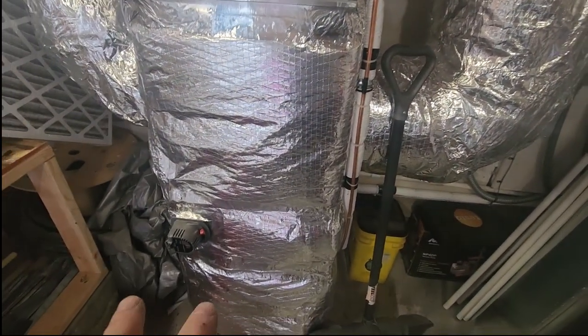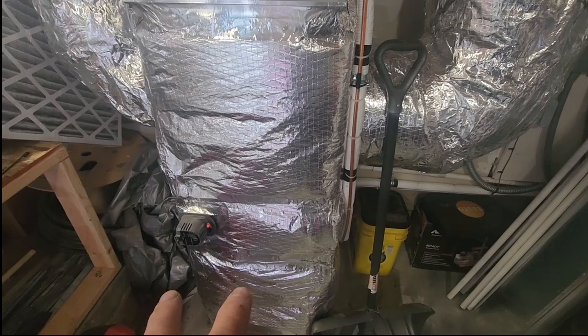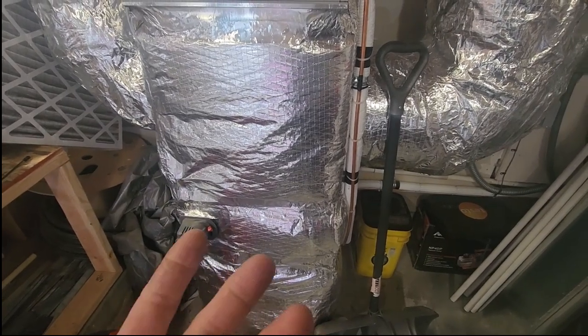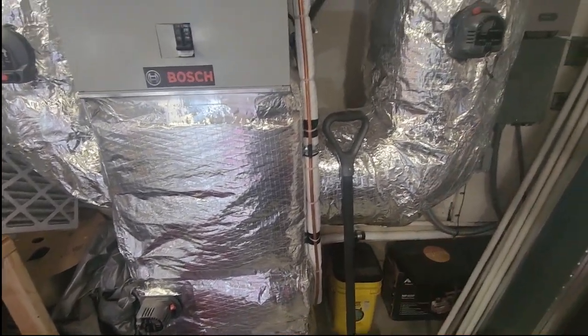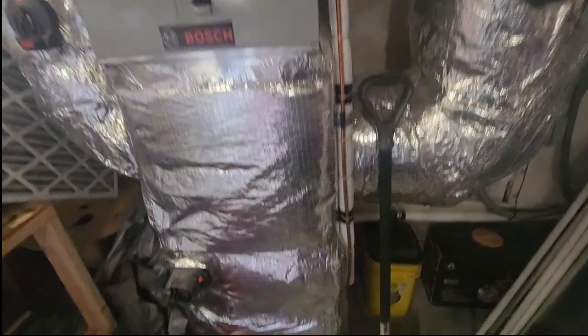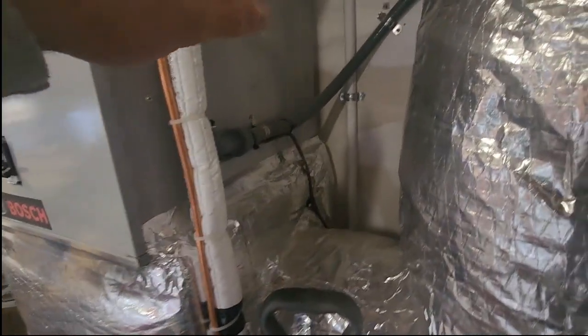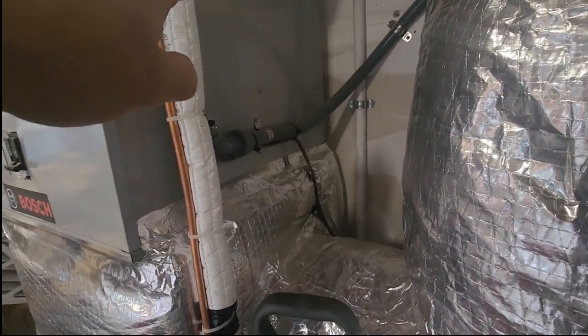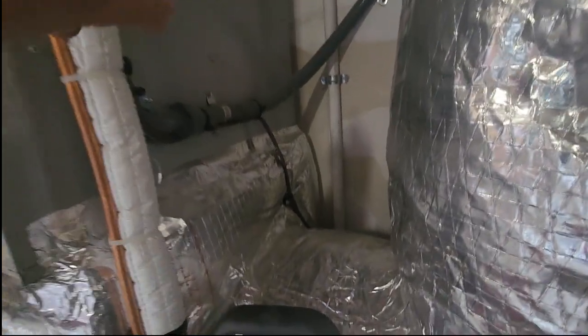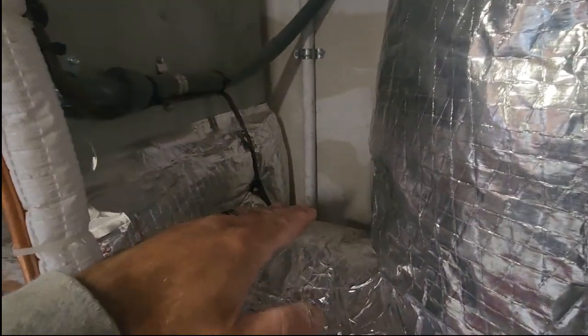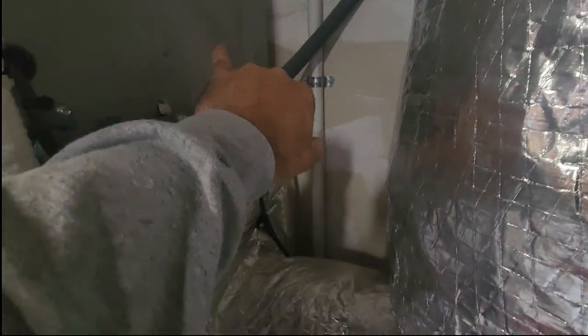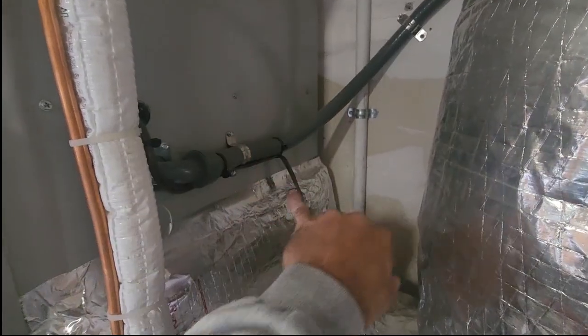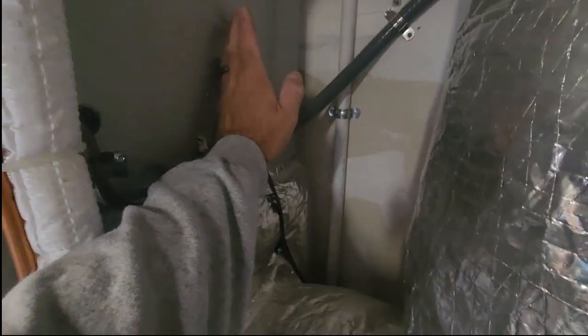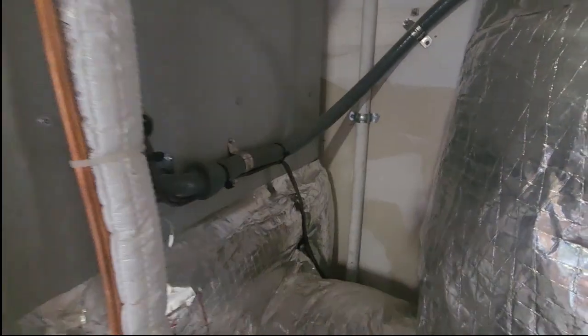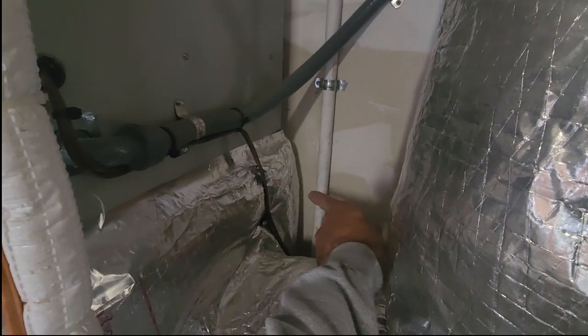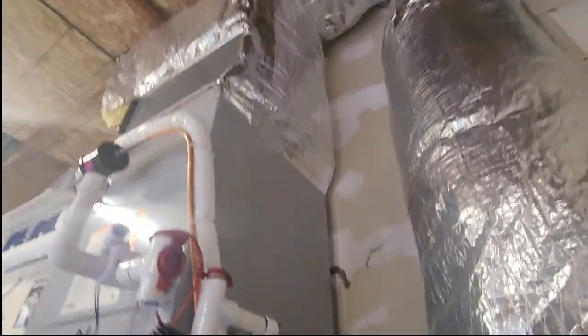I'm going to force this thing into high fan, which will be cool. I'll put both zones into cool. On these air handlers, you want to be past everything, so we want to be as close to the furnace as possible. The supply on these air handlers is back here, and it only goes out to about here or so. So we want to get our static pressure tip in there, and then our return is self-explanatory.